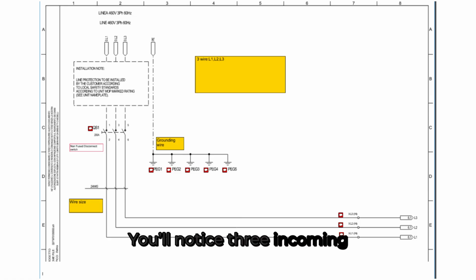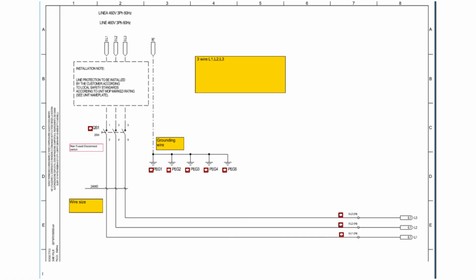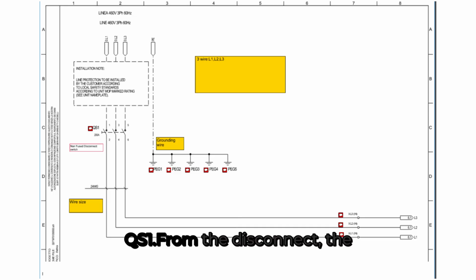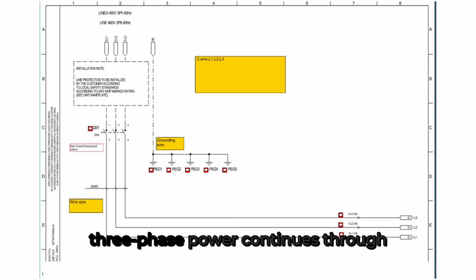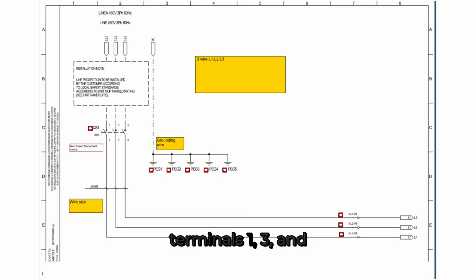You'll notice three incoming power lines labeled L1, L2, and L3, along with a ground terminal labeled PE. These represent the three hot conductors of the three-phase supply and the protective earth ground. It includes a non-fused disconnect switch, shown as QS1. From the disconnect, the three-phase power continues through terminals 1, 3, and 5, exiting on 2, 4, and 6, and then connects to the terminal block points XL1, XL2, and XL3 inside the unit. Wire size is 2 AWG.